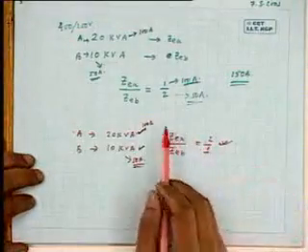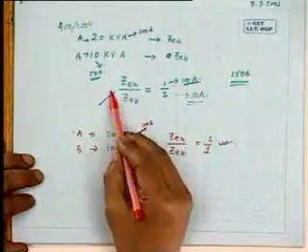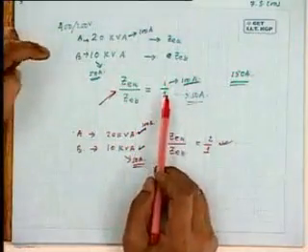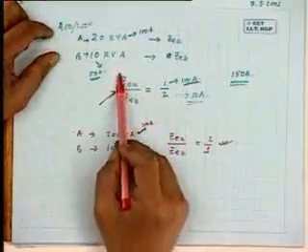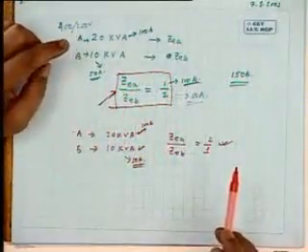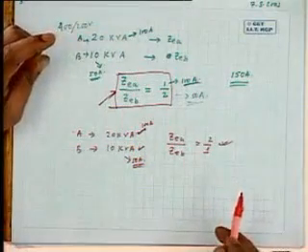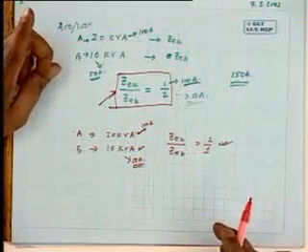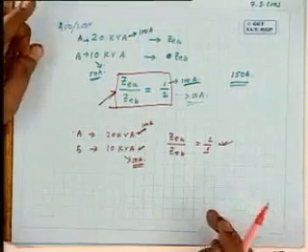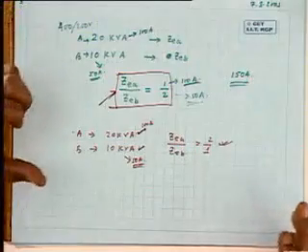Therefore, how much current they will share depends upon this crucial ratio, and you have to select the ratios correctly. That is why we say that the impedances should be inversely proportional to their kVAs.